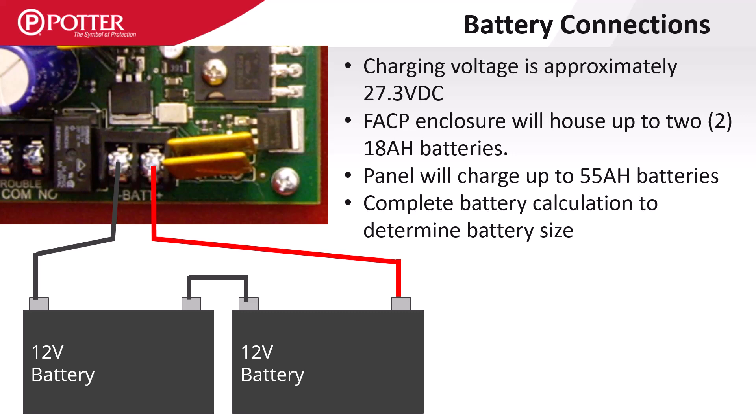The PSN-1000 can house 7 or 18 amp hour batteries but is not deep enough to house 12. The charging circuit has the same characteristics as the control panels: 27 volts DC with a max load of 55 amp hours of batteries.